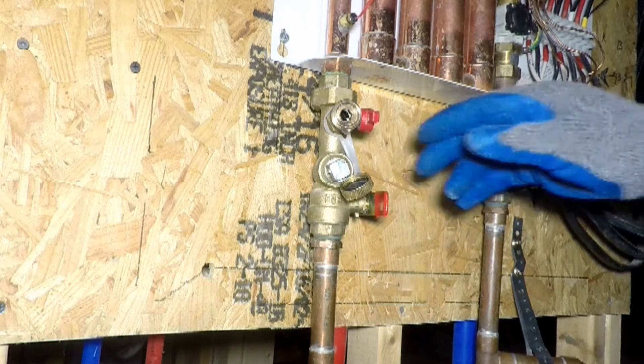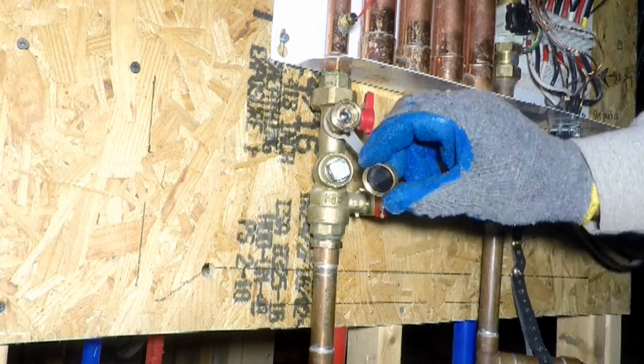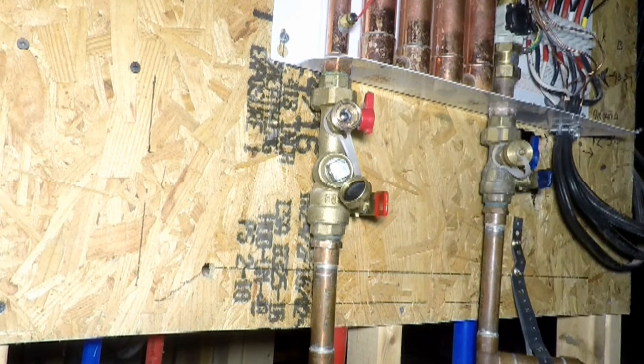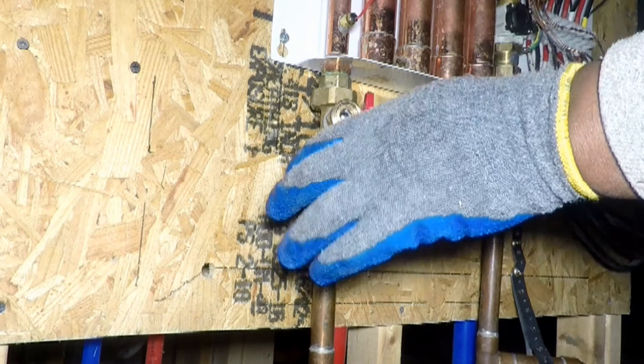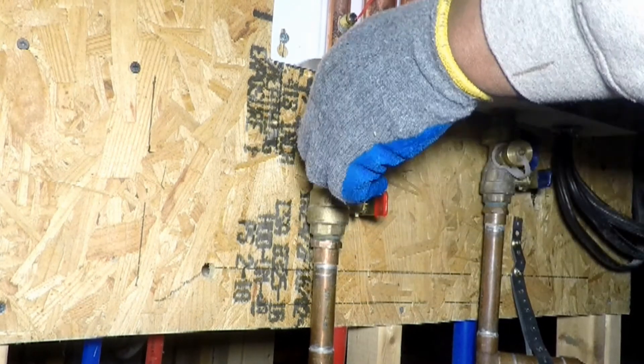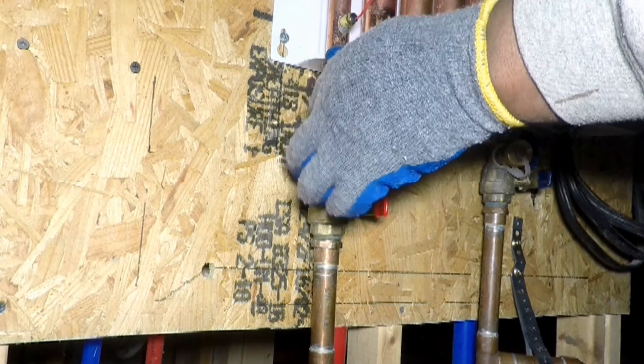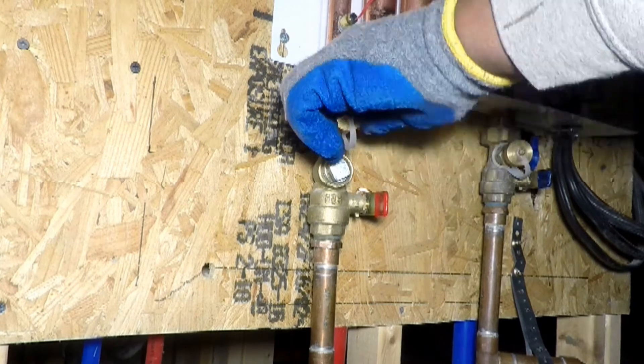The unit is now put back in normal operation by resetting the positions of the cold and hot water service valves. Before powering the unit, turn the faucet on, set it to the hot water setting, and allow water to flow through the heat exchangers. Do this for about a minute.